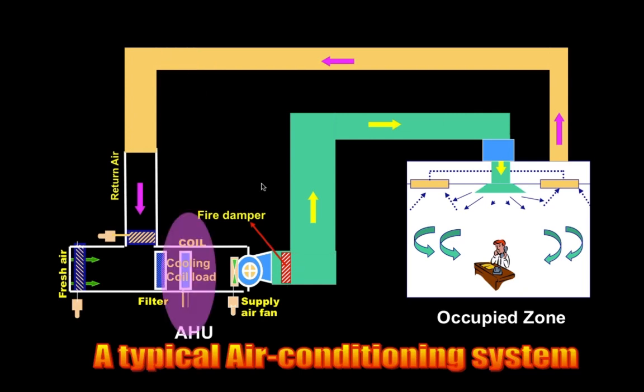And then I would like to highlight here that the cooling coil, which does an important job in trying to address the sensible cooling load and the latent cooling load, is the critical part of the entire design process. If the cooling coil doesn't do a good job, you are going to have conditions that are not comfortable in terms of temperature and perhaps also in terms of humidity. So this is the basic design that we have for most buildings, in fact all air-conditioned buildings in the tropics. And the larger the building gets, the more complicated the design of the air handling units becomes. And I would just like to state that let's look at this typical system, a typical air handling unit.